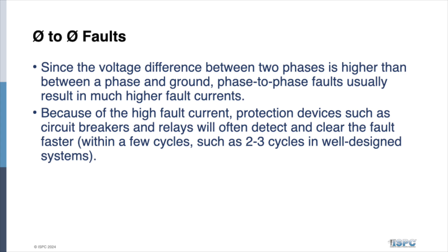But because of the high fault current, your protective devices are going to operate about twice as fast if you are short-circuited phase to phase, okay? Normally about 2 to 3 cycles, okay? A cycle's about 16 milliseconds, just a little over, right? So very quickly, if you're grounded phase to phase to phase in a fault and then to ground, your protective devices operate, and that's really what we're trying to do.